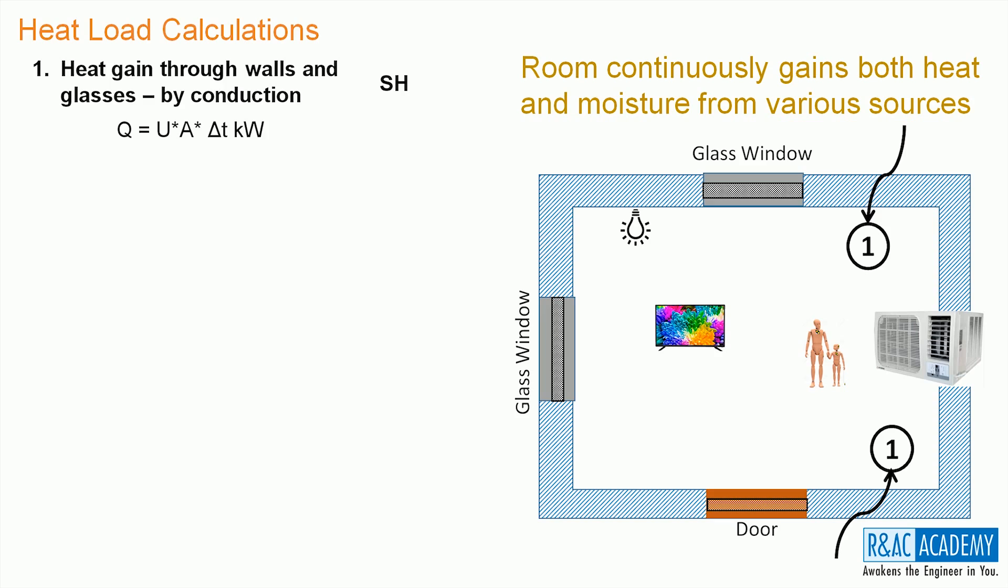This is the expression that is used to compute the heat gained by the room through this source. Q equals UA delta T gives us the heat gain through walls and glasses in kilowatts. Here, U is the overall heat transfer coefficient: 1 by HI plus T by K plus 1 by H0. HI, K and H0 can be had from the data tables. T is the thickness of the wall or thickness of the glass.